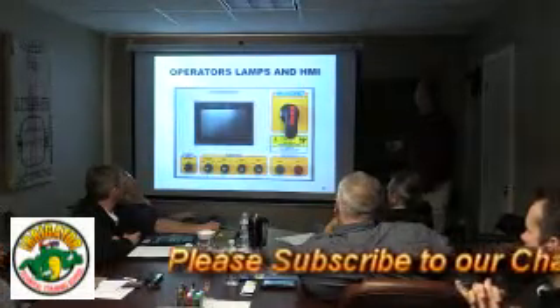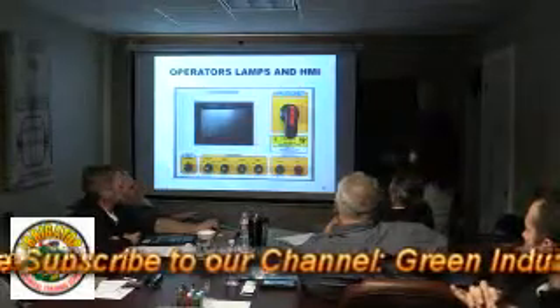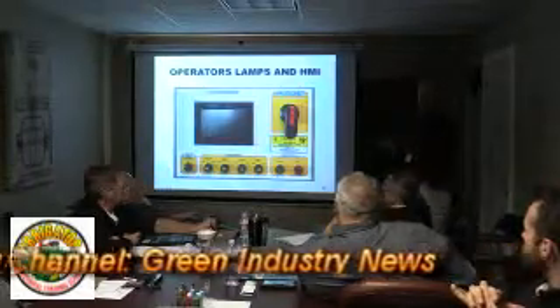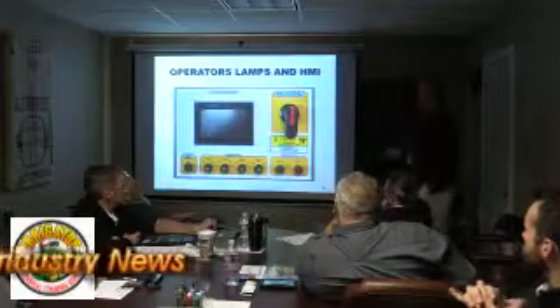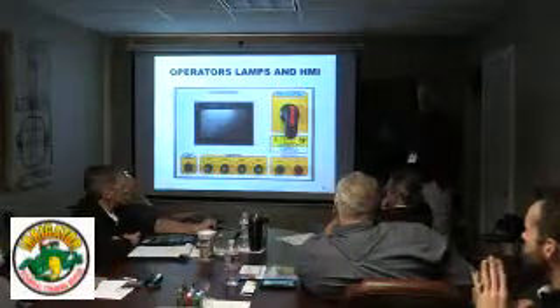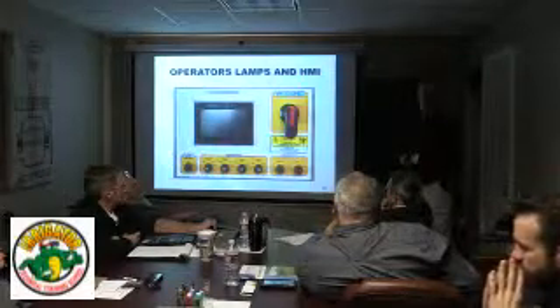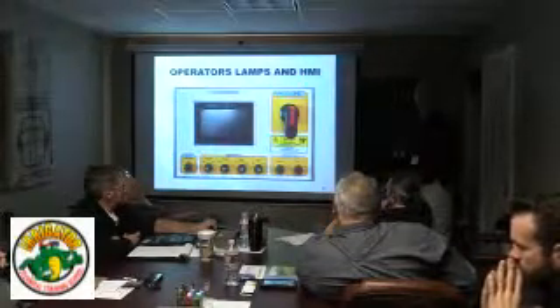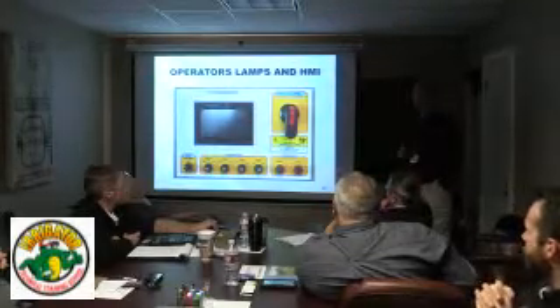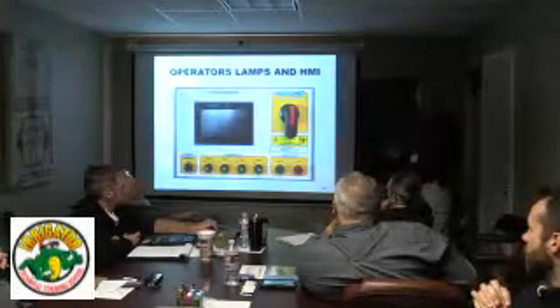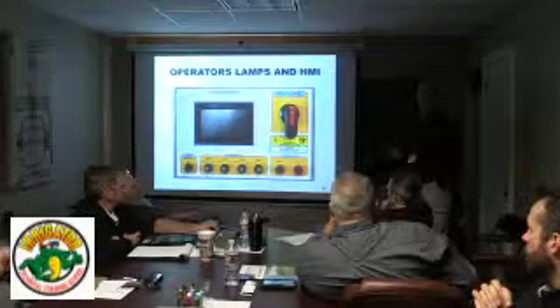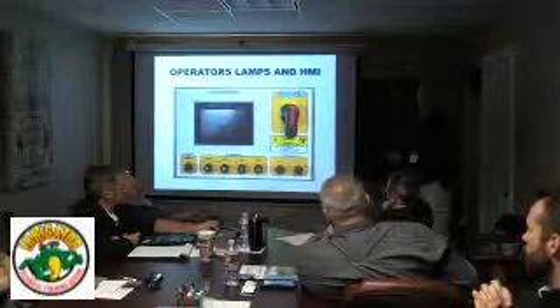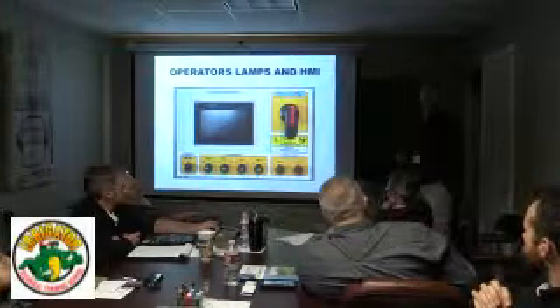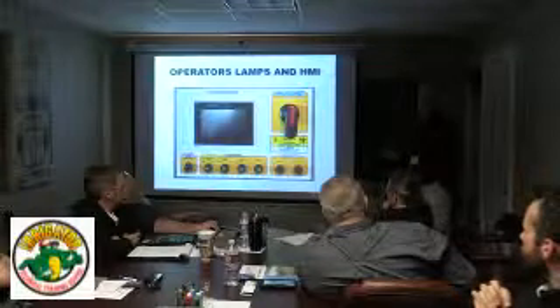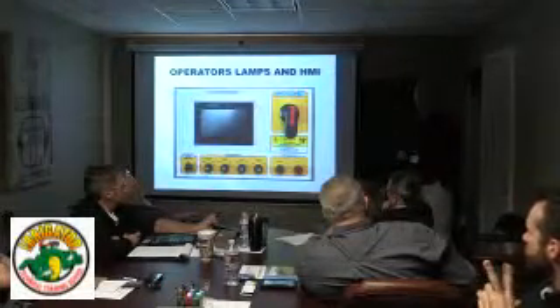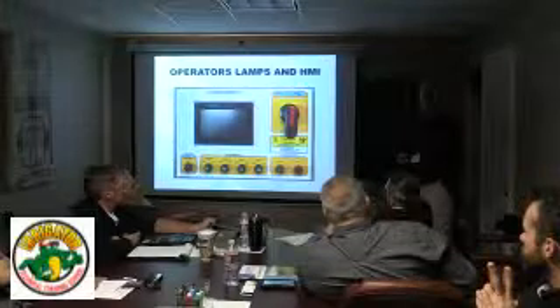Another thing I want to point out on this one too is a lot of times if we're troubleshooting, especially if we get a VFD drive fault, the PLC or the touch screen will display a fault, but the drive's got so many faults that we don't know what every single fault is, and so it might just display VFD fault. In that case, you're going to have to open the door and read the fault on the drive. In many cases, if you turn the power off to open the door, you've reset the fault in the drive. And if that condition doesn't occur, you have to go into the fault log and that. So, and for other reasons, sometimes it's handy to be able to open the door with the power on.